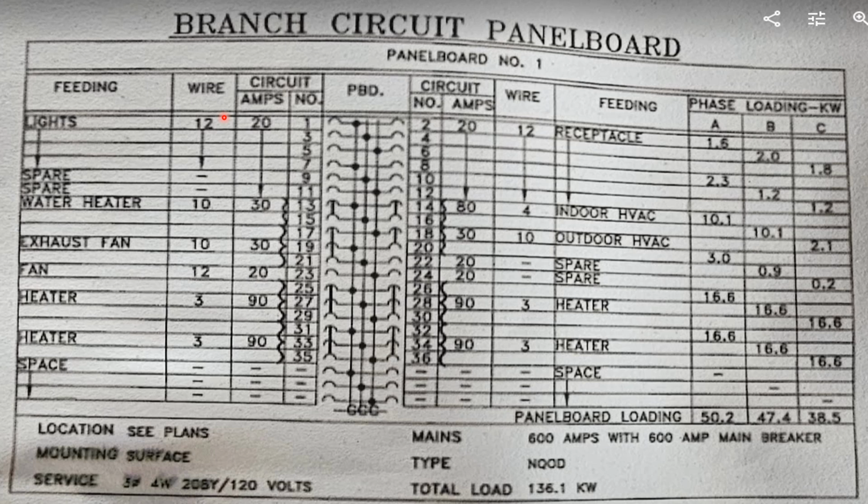There's a lot that we can learn right here from the panel schedule. We're looking down here. We can see that it's 3-phase, 4-wire, 208. That's going to let me know about my service as I'm doing my estimate. They want 600 amp mains with a 600 amp main breaker, which I can calculate all the size conduit, wire, grounding electrode conductors, grounding electrodes, how we're going to tie this whole thing together.